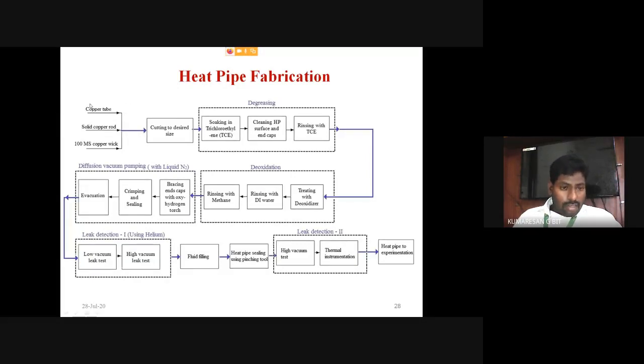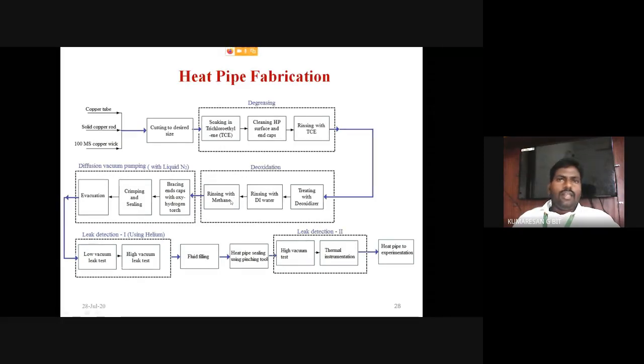Then these components are taken for the degreasing process to clean the heat pipe. Then they are taken for the deoxidation process, because once we fill the copper tube and the ends are sealed, we don't have the provision to open and clean the heat pipe frequently. So that's why the deoxidation process is done initially. Then it is treated with the deoxidizer, and these materials are mixed with the methane fluid. Then it is kept for 1 or 2 days for the deoxidation process.